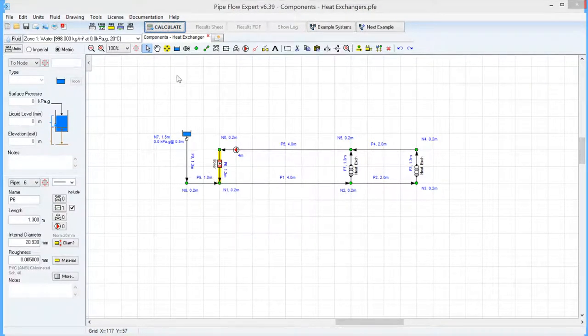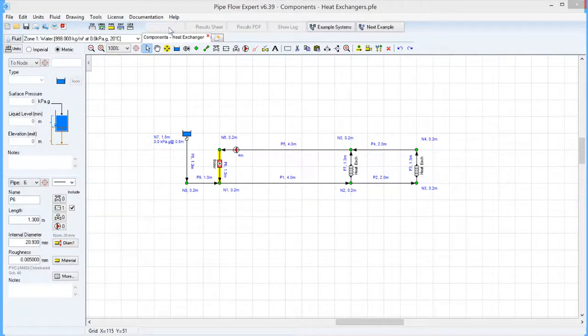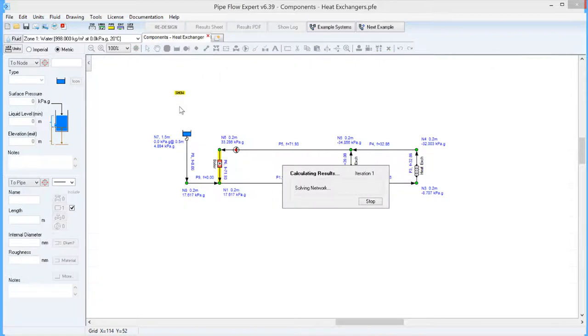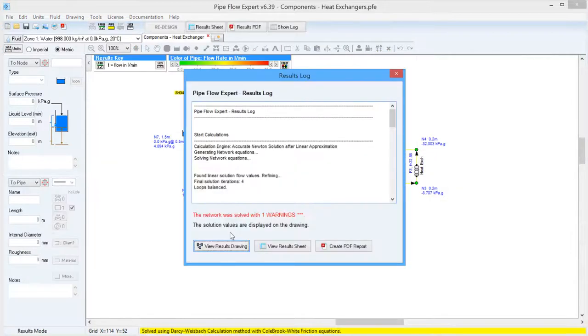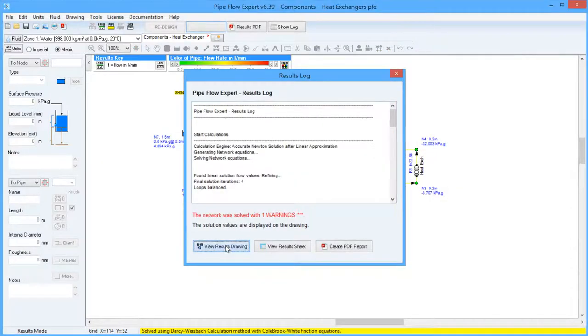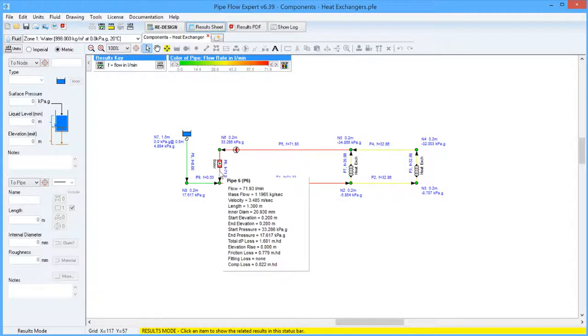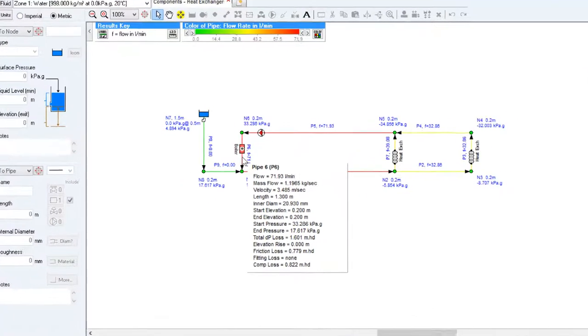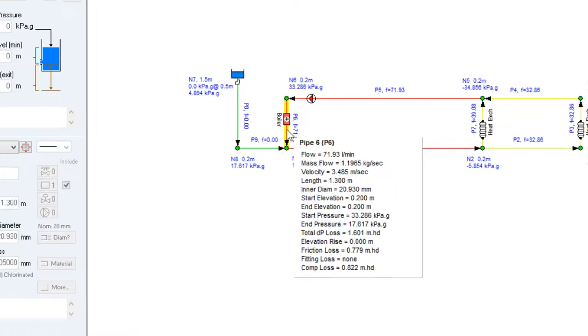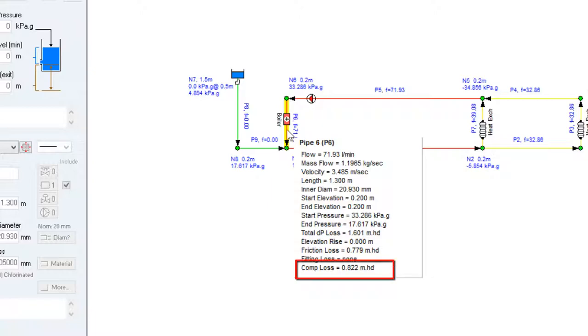So we can go ahead and solve this system now and view the results drawing, and then we can hover over a pipe and view the calculated results for that pipe. In the case of this pipe with the boiler on it we can see a component loss of just over 0.8 metres head.